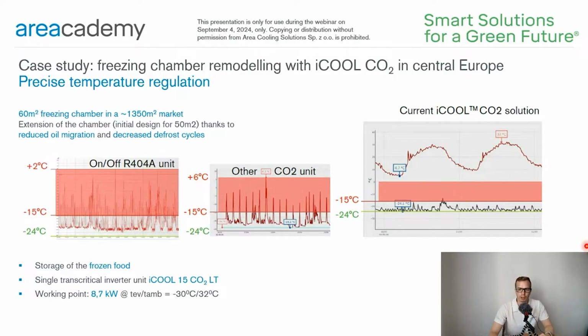Finally, inverter transcritical iCool CO2 units by Area Cooling Solutions were used. And you can see in the remote control recording on the right that the temperature practically does not exceed the critical point. It's thanks to the inverter technology. The unit provides very precise temperature control and adjusts the cooling power so that the conditions inside the chamber are suitable all the time.